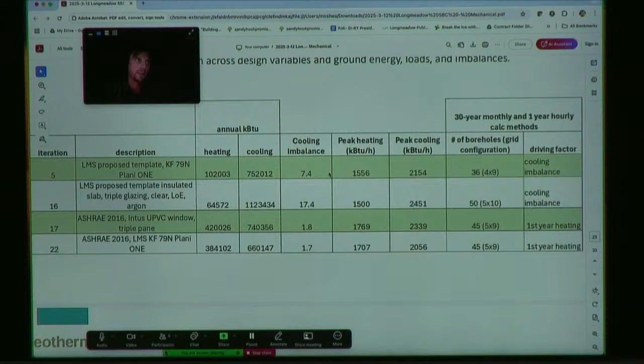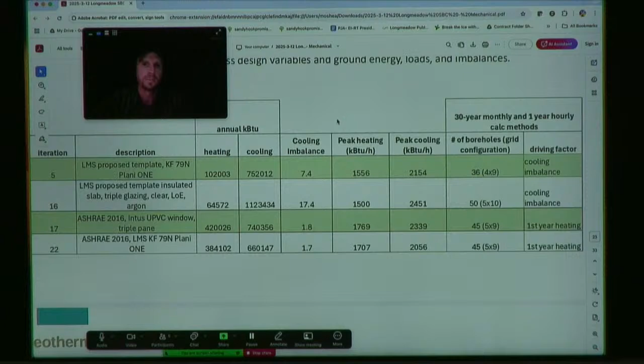That would be because the peak cooling demand is occurring outside of the summer. It's occurring when the school is occupied, most likely in either August or June, right? So probably July might be your design day. And you have to remember, these are loads to the ground, so it's more or less the condenser load on the building. So all of the compressor heat and all of the pump heat is also included in the cooling load. So that drives the cooling load up. Okay, so it essentially hurts the cooling load and helps the heating load. Yep, got it.